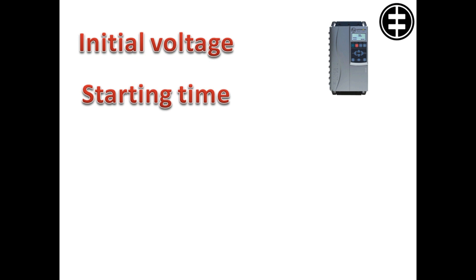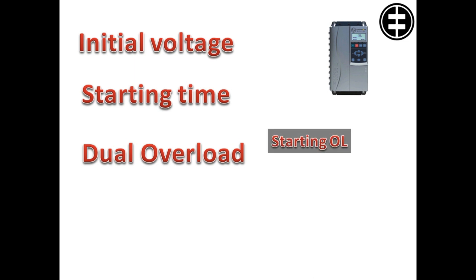Another feature in the soft starter is for better motor protection. In some soft starters, you have the ability to set two overload settings: one to monitor the motor during startup, and the second to monitor the motor during operation. This is because of the different motor current characteristics in both stages.